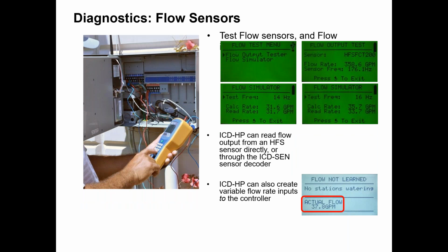You can do some diagnostics with flow sensors. In that screen, you can do an output tester, you can do an output simulator. You can actually program sensor decoders. On this one, it is a 2-inch HFS FCT 200, and you can actually see your flow rate, and you can actually simulate it to check your clock to make sure everything is working right. And if something is turned on, you can look at your flow rate too, and you can see in the bottom right screen right there, that's exactly what he's looking at. You do have to tell it also where you're looking at it, either if you're testing the controller or testing the decoder. That's kind of key, so you know exactly what you're testing.